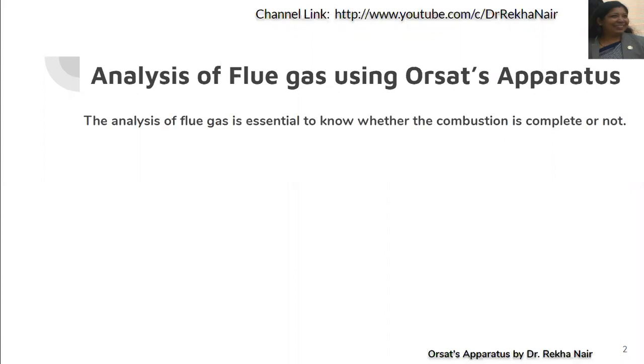It is essential to analyze the flue gas because we must know whether the combustion is complete or not. If the combustion is complete, then the product will generally be carbon dioxide. If there is carbon, it will be converted into carbon dioxide. If there is hydrogen, it will be converted into water. If there is sulfur, it will be converted into SO2, and so on.